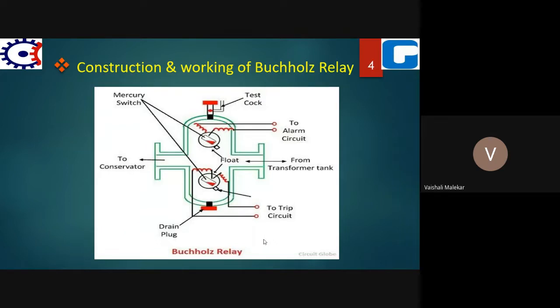Now we'll see the construction and working of this Buchholz relay. The Buchholz relay is a type of oil and gas actuated protective relay, and it is universally used in oil immersed transformers having a rating of more than 500 kVA. This relay is not provided in transformers having a rating below 500 kVA, because of economical consideration. It is used for the protection of the transformer from faults which occur inside the transformer. Such faults may be short circuit faults like inter-turn faults, incipient winding faults, and core faults, which occur due to impulse breakdown of the insulating oil, or simply the transformer oil. The Buchholz relay will sense such faults and close the alarm circuit.